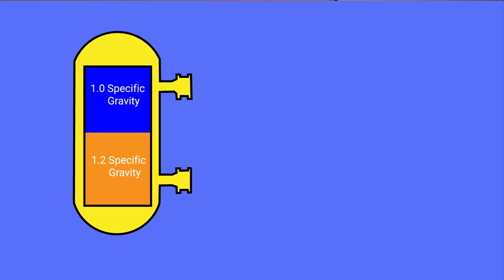So now that we got the rules that we need to follow out of the way, let's figure out the calibration values also known as the LRV and the URV. On this vessel, we have two liquids containing specific gravities of 1.0 and 1.2 just to keep it simple.